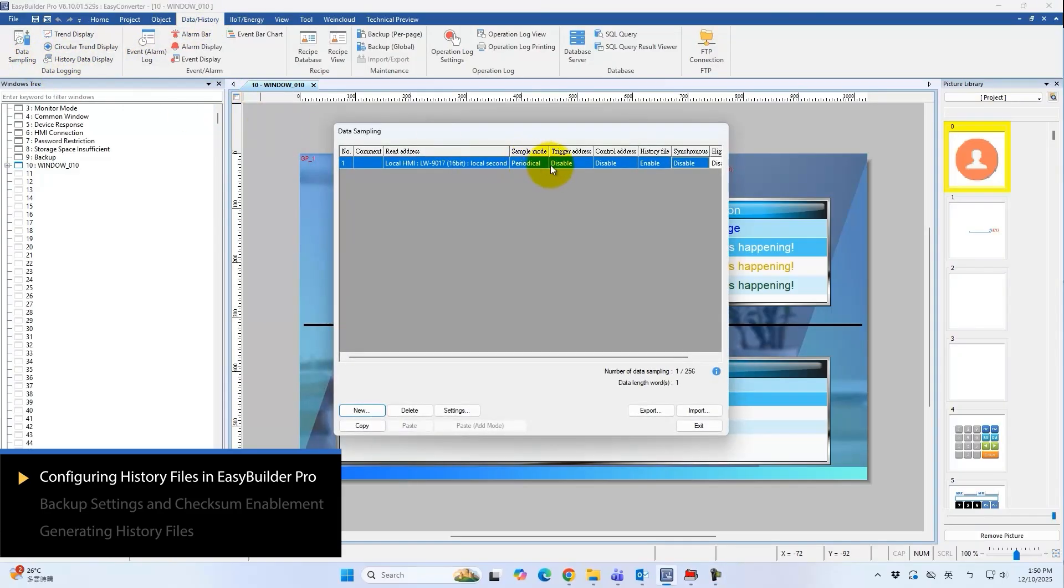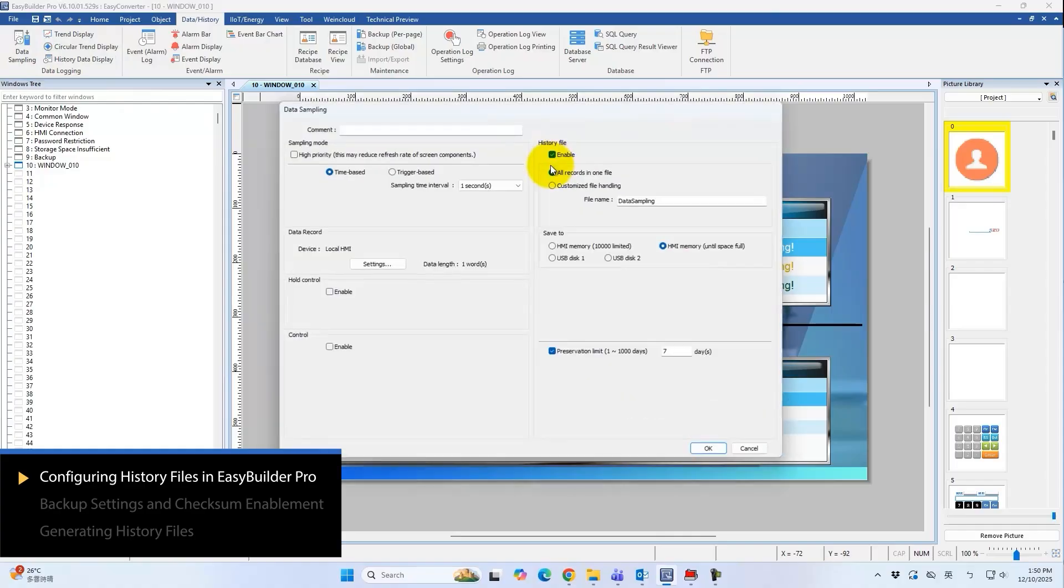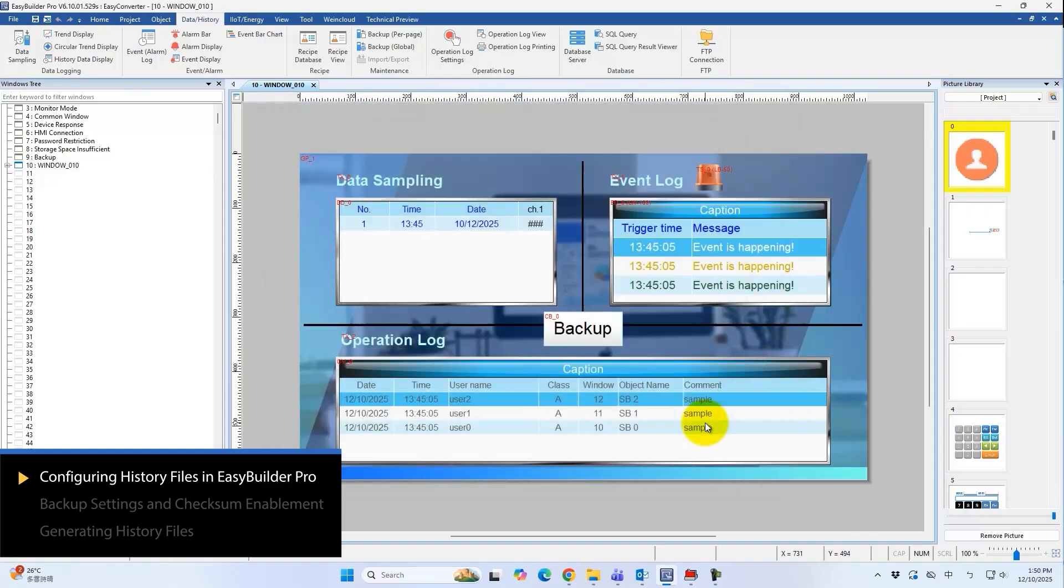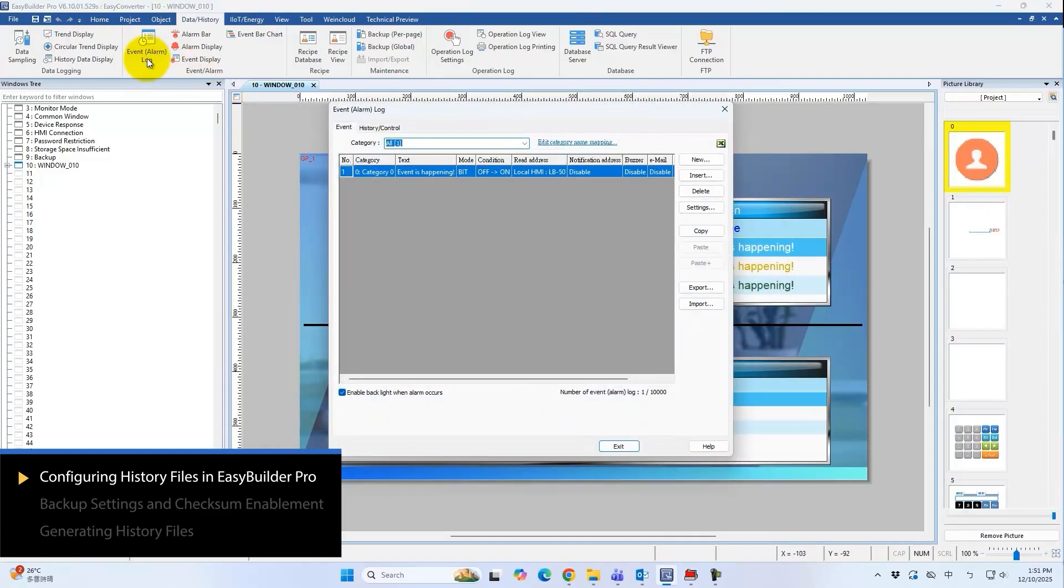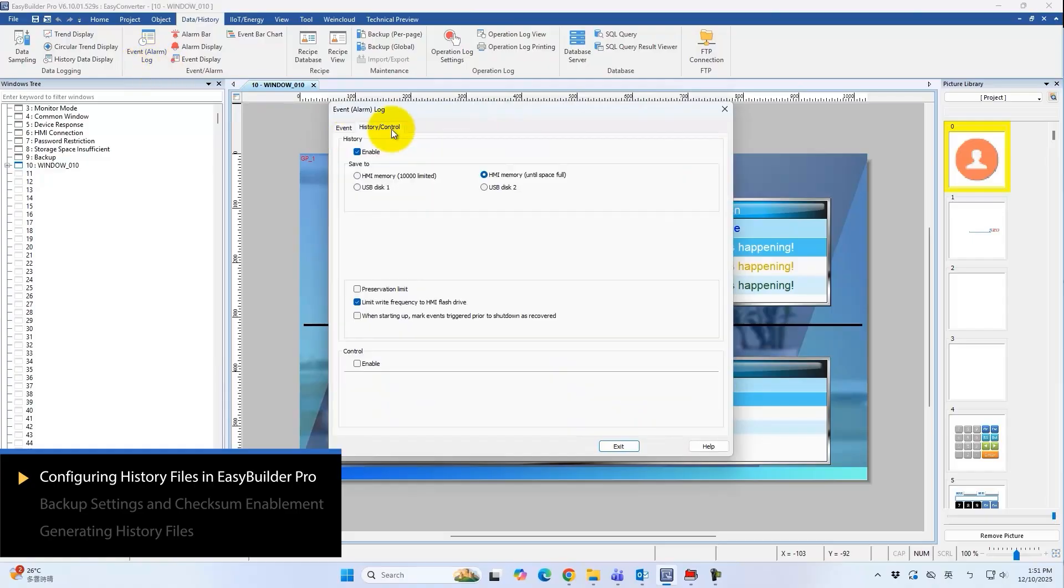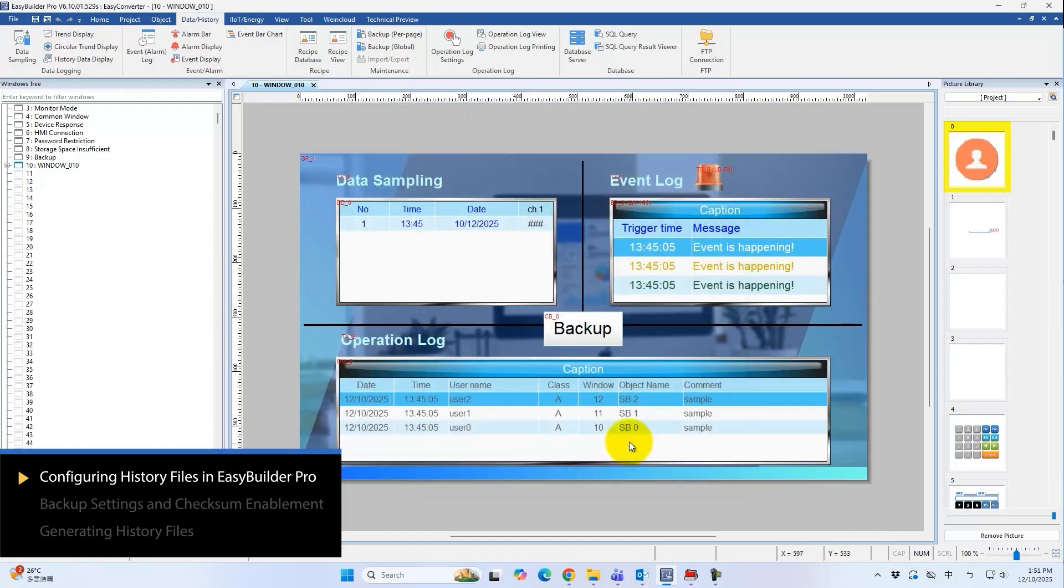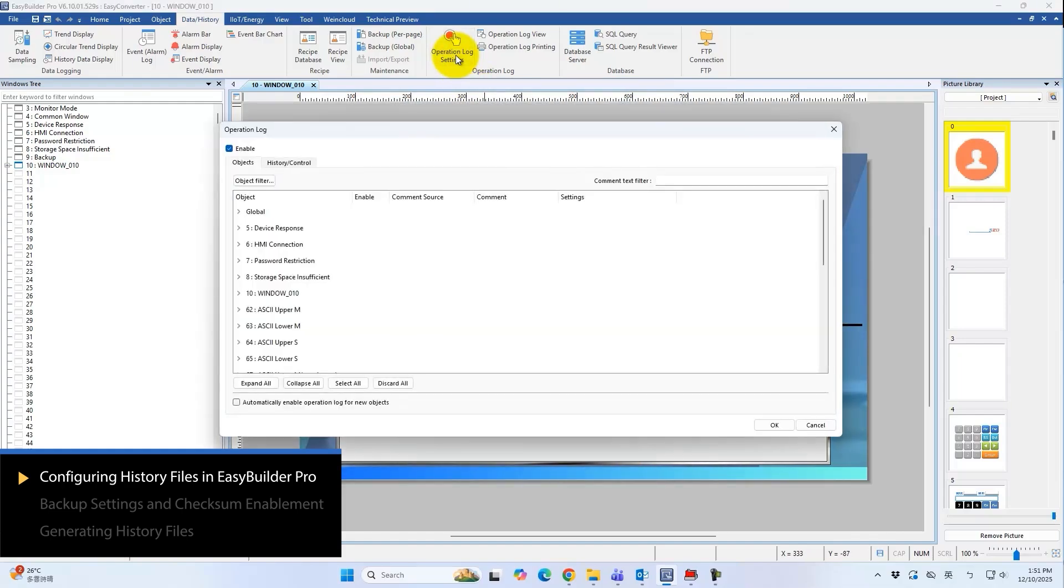In EasyBuilder Pro, make sure the history file feature is enabled so that the HMI can generate and save these files during operation. Likewise, enable both event log and operation log features before use. These are the basic settings required to create historical files.